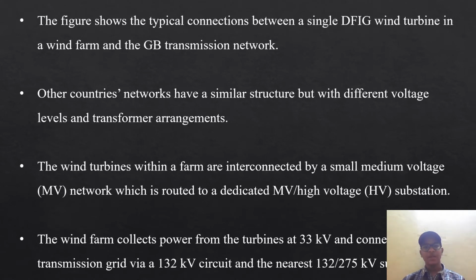The figure shows the typical connections between a single DFIG wind turbine in the wind farm and the GB transmission network. In other countries, the network has a similar structure but with different voltage levels and transformer arrangements. The wind turbines within the farm are interconnected by the medium voltage (MV) network, which is routed to a dedicated MV/high voltage substation. The wind farm collects the power from the turbines at 33 kV and connects to the transmission grid via 132 kV circuits and the nearest 132 to 275 kV substation.